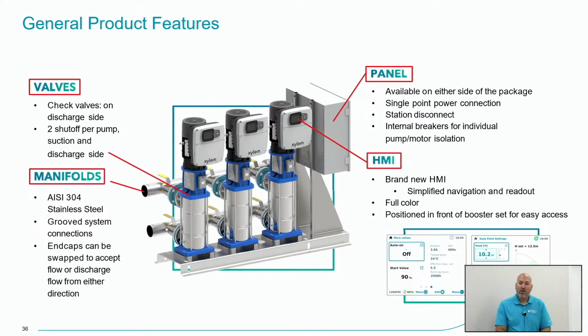It's a single point power panel there. You can decide what end you want it on. If this has to be in a certain spot for a mechanical room or space, you can choose the left side or right side for that panel to be installed on. But much simpler and easy to navigate and use with that Hydrovar X HMI now and that software compared to the historical 5th generation Hydrovar that these packages used.